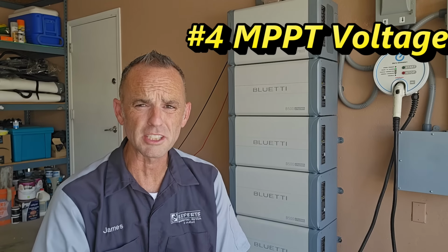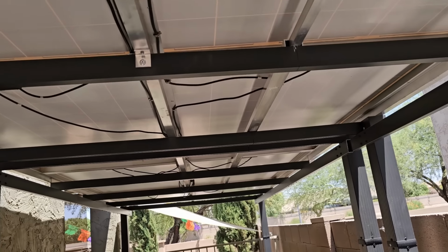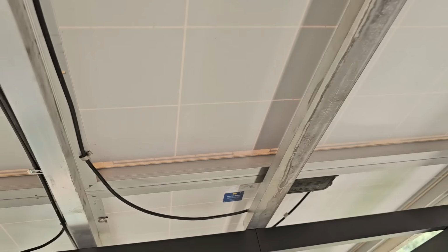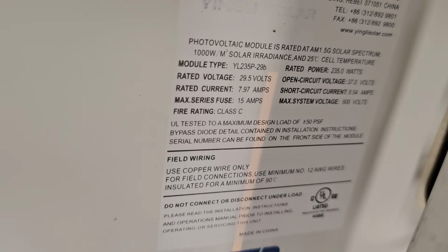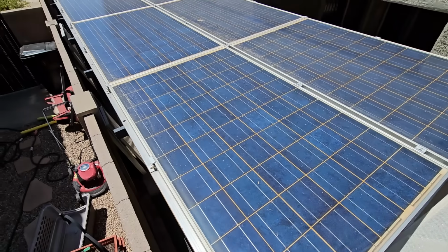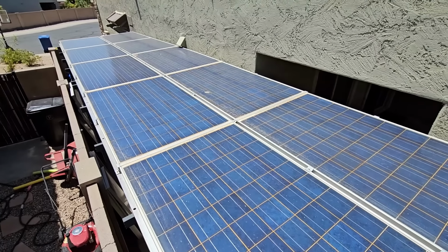That's my complaint. My second complaint is the MPPT charge controller voltages. There are two MPPT charge controllers on it, a 3,000 watt and a 6,000 watt, for a total of 9,000 watts capability, which is great and fantastic. The minimum voltage needed is 150 volts DC in order to turn the charge controller on, and it can go up to about 500 volts. Bluetti was basically recommending at least 250 to get it going, and that's been my experience. Even though I have voltages on my solar array that are around 200-ish, it still does not kick on that solar charge controller until I get probably about 260 volts. That's a very high voltage. I have 10 panels, and it's barely kicking on until I have direct sunlight on it.